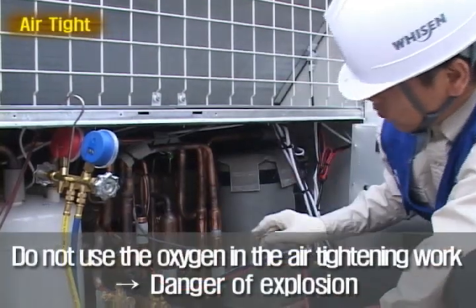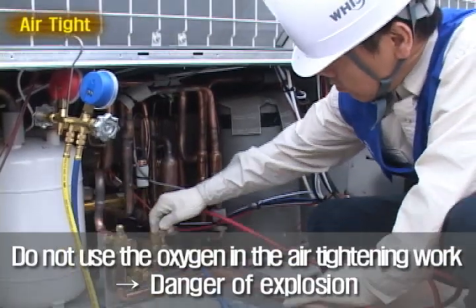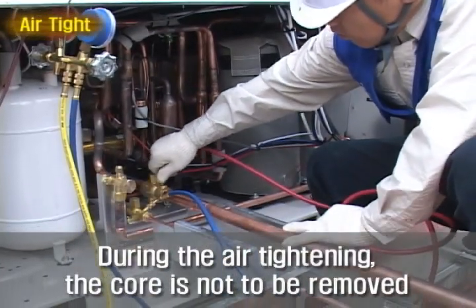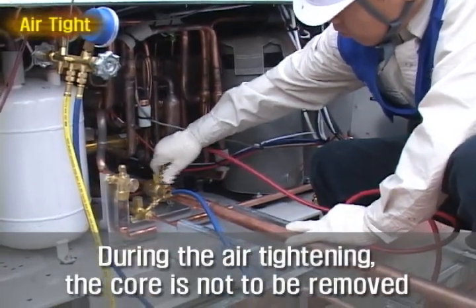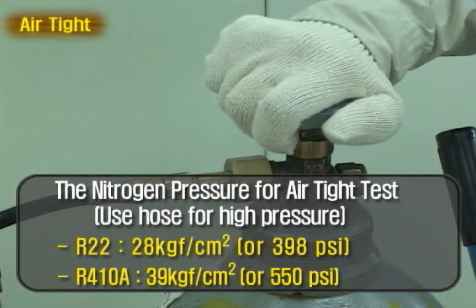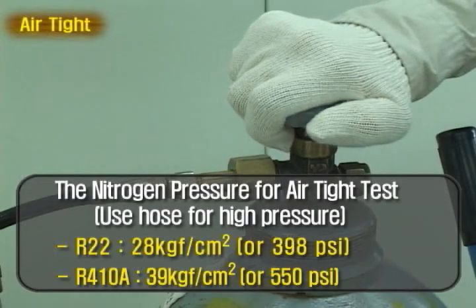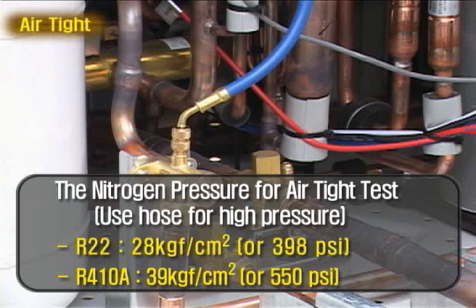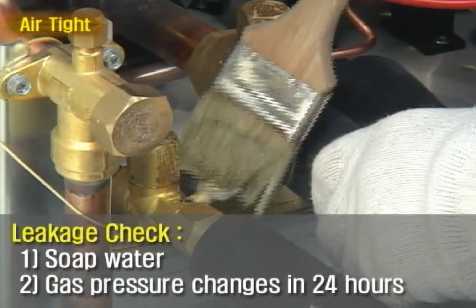For one outdoor unit model, charge nitrogen gas after connecting the high and low pressure service valve, pressure gauge and nitrogen tank using a high pressure hose. For 2 or more outdoor unit models, charge nitrogen gas after connecting the sharing pipe additionally. Check the leakage with soap bubbles and confirm the pressure maintains the same for 24 hours.